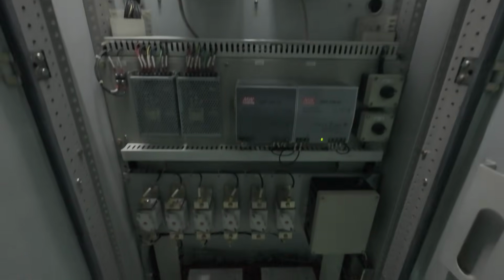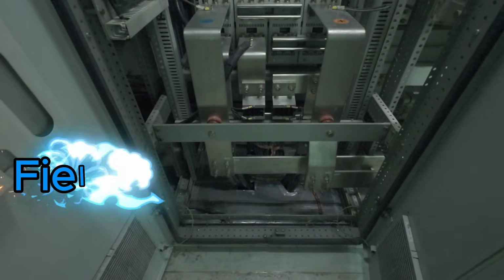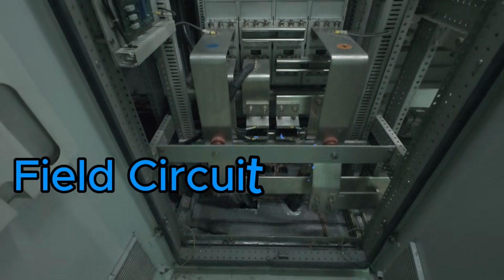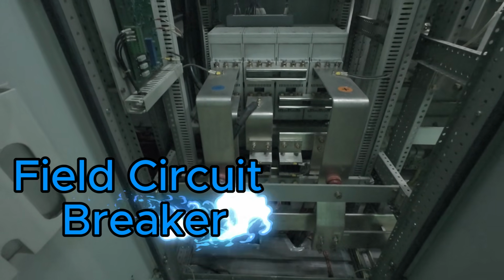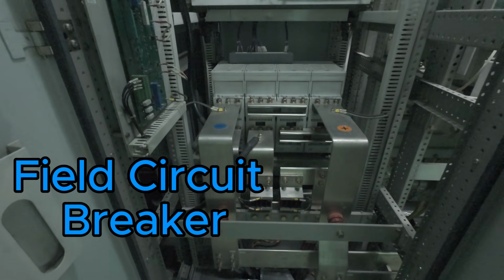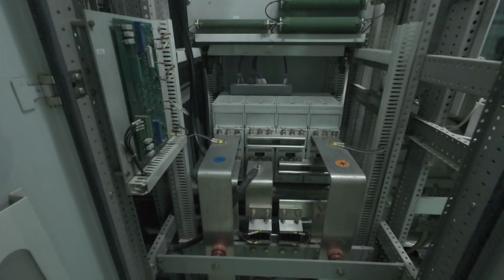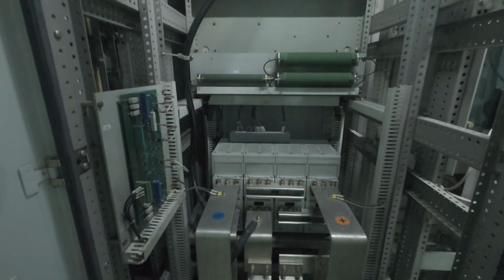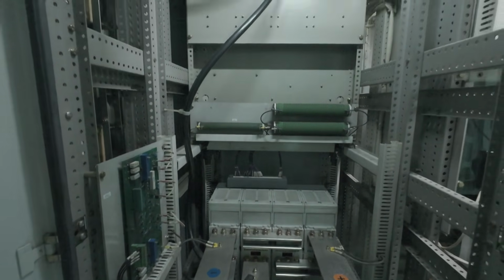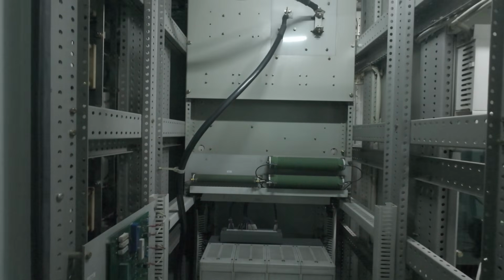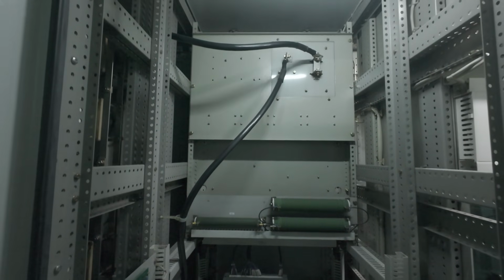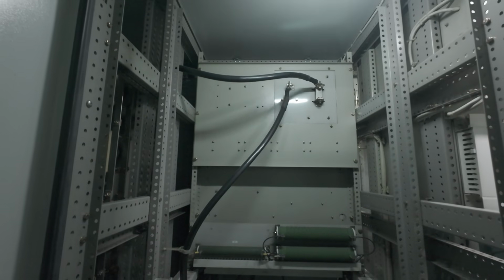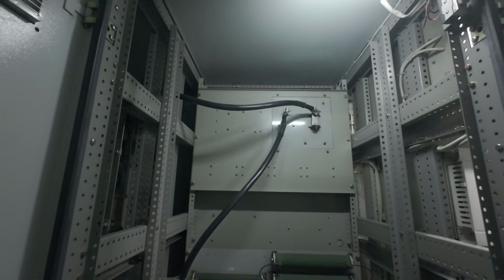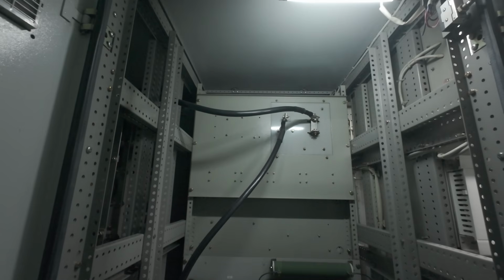And finally comes the protection system, the field breaker and de-excitation circuit. Because the rotor is basically a giant electromagnet storing enormous energy, if the generator trips during an emergency, that magnetic energy must be removed safely. The field breaker disconnects excitation instantly, while discharging resistors safely collapse the magnetic field within milliseconds.